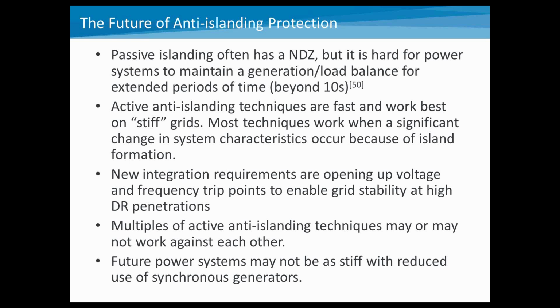One of the things that we don't have a lot of work on is multiple active anti-islanding techniques. They may work with each other. They may work against each other. Kind of depends on which techniques they're using. And as we look to future power systems, if we lose a lot of synchronous generation, they may not be as stiff. So we may be forced in general to allow distributed resources to operate in a bit wider range of voltage and frequency settings.